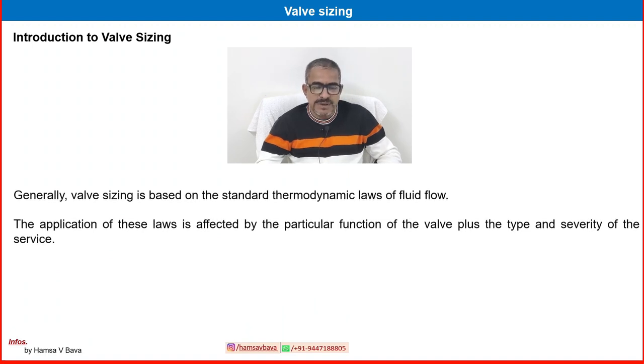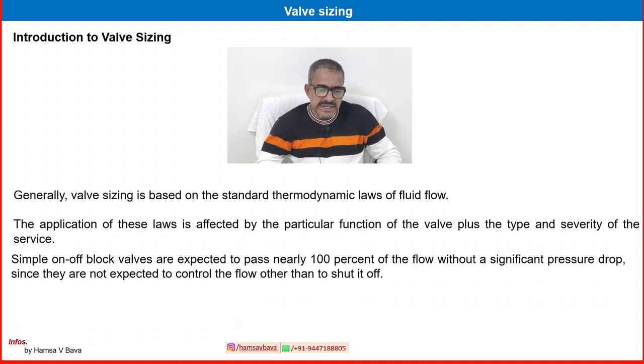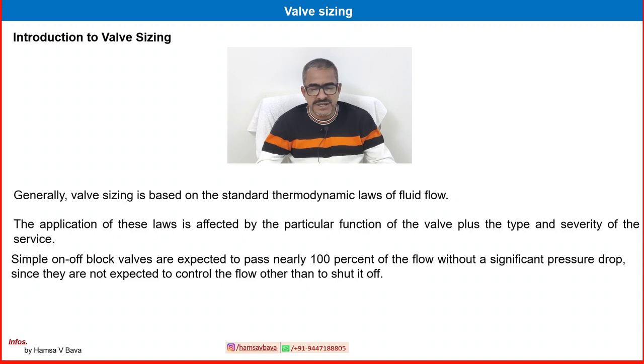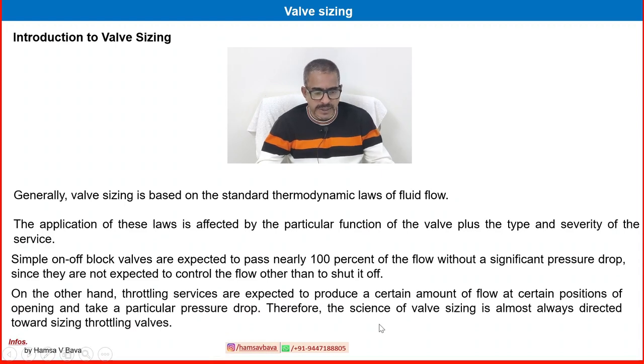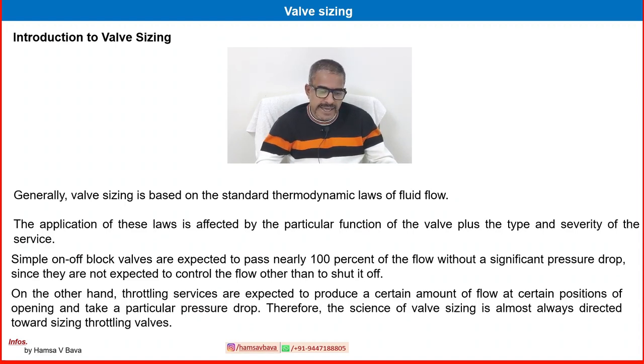Generally, valve sizing is based on the standard thermodynamic laws of fluid flow. The application of these laws is affected by the particular function of the valve plus the type and severity of the service. Simple on-off block valves are expected to pass nearly 100% flow with minimum pressure drop, since they are not expected to control the flow other than to shut off.